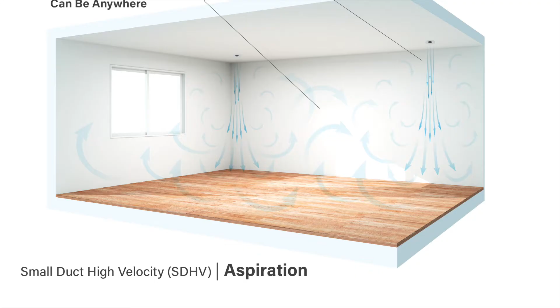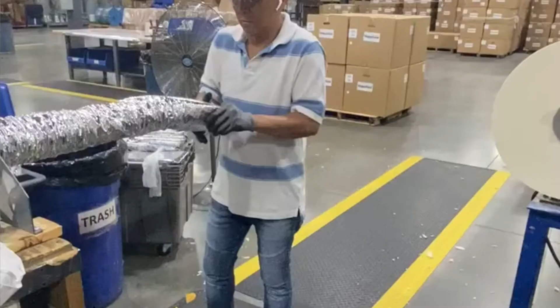Well, the Unico has less air. We're delivering about half the volume of air at twice the speed. But it's a mixing effect, and it's a very quiet system. That duct that Scott was holding up, as an example, that's our small delivery. So you mentioned the rectangular plenum. Every main plenum is insulated, because we're running such great dehumidification. We need to insulate it, make sure we don't have a dew point issue. There's Scott again, very nicely done.